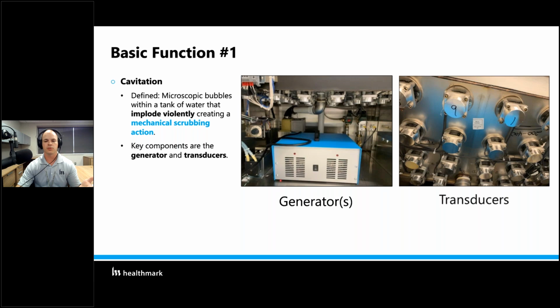Which then leads me to this screen, which, to kind of further break it down, if you are trying to remove soil with this basic function number 2, I call it, cleaning, removing soil, you have to have several factors working properly in order to do it the right way. And that would be cavitation has to be present, but there should be detergent. And because you have detergent in there, you should have the right temperature in accordance with the detergent IFU. And then you're going to need the right exposure time.